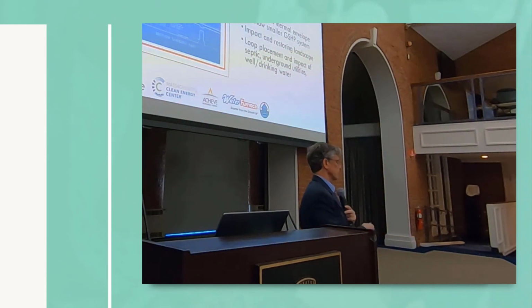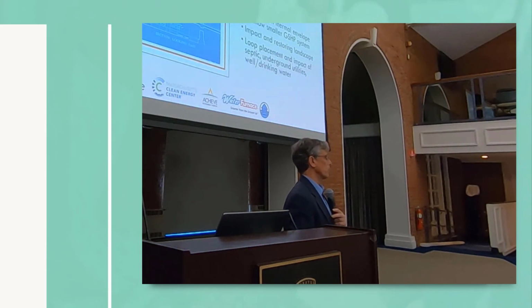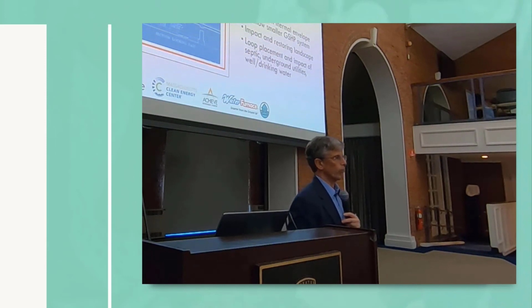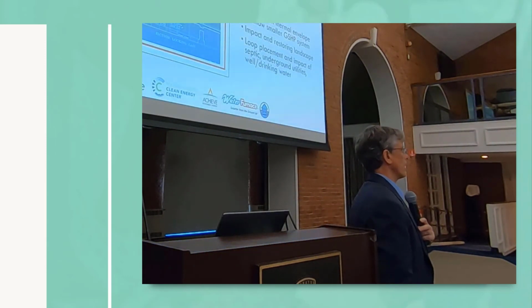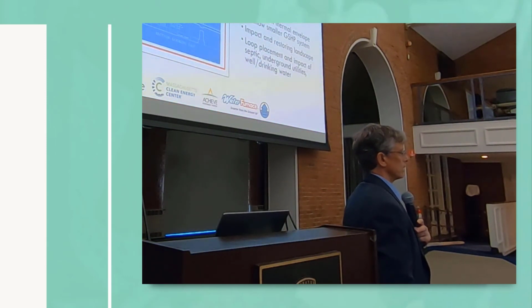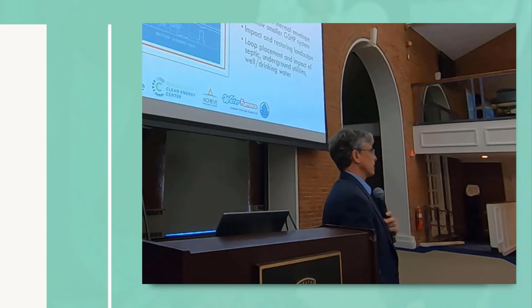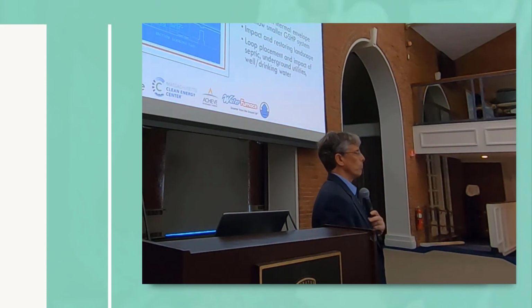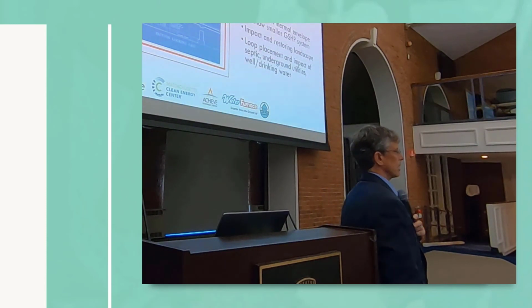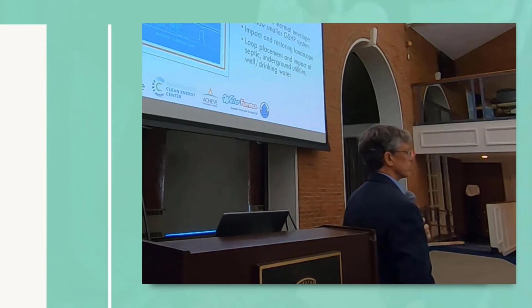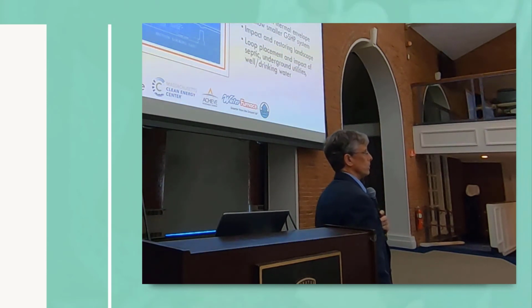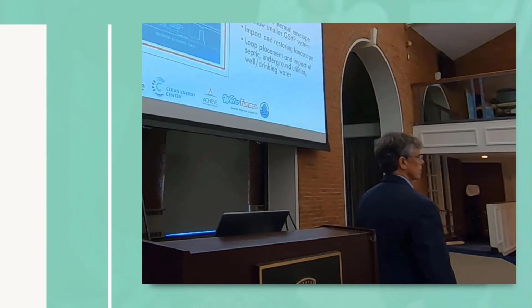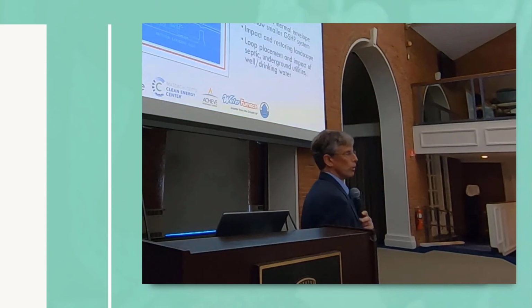So with closed loop systems, we really would love to hit the unfortunate dry conditions that someone would have if they had a failed water supply or irrigation well. If we hit conditions that would give somebody 100 gallons a minute, then that water has to be contained, managed. It can make things messier because there's just that much more mud when you're dumping thousands of gallons of water on the ground and trying to infiltrate it. We will sometimes have to bring in a storage tank or something to control it, especially in an urban area.